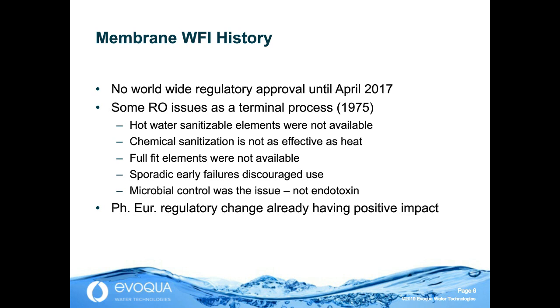And although there was pretty good success in these alternative RO systems, reverse osmosis was not nearly as advanced as today. The RO elements at that time were not hot water sanitizable, and chemical sanitization can be effective, but it is not nearly as effective as heat. The membranes were not machine-made at that time. They were not as consistent in quality, and full-fit elements were not available. That is the construction where some water is allowed to flow around the outside of the element, between the outer wrap of the element and the pressure vessel, and that makes a big difference in micro control.